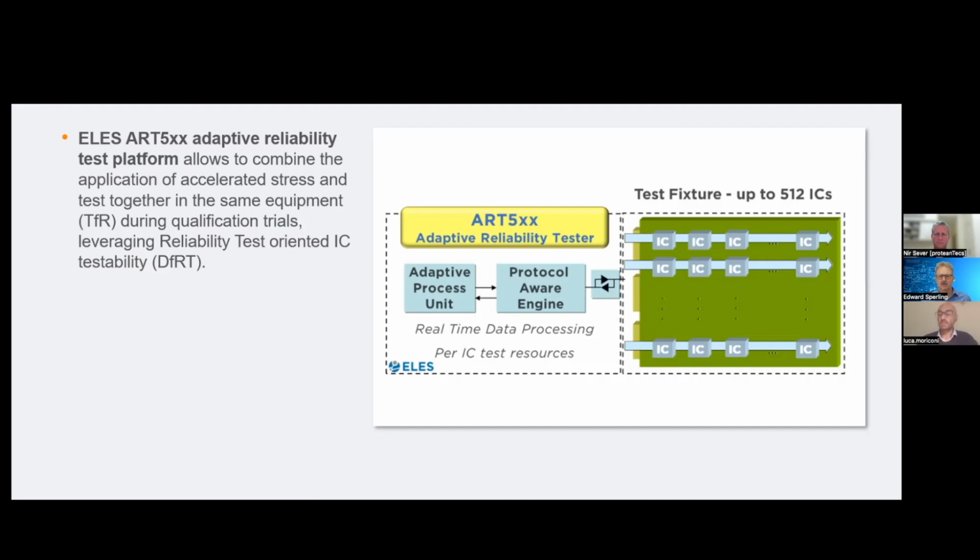Of course, the other aspects are related to thermal management. We are now facing devices that during qualification dissipate up to 1,000 watts. So we need a very high temperature accuracy also for this kind of devices and at the extreme conditions of the HTOL. In this case, we developed a liquid cooling thermal active control in order to do this.